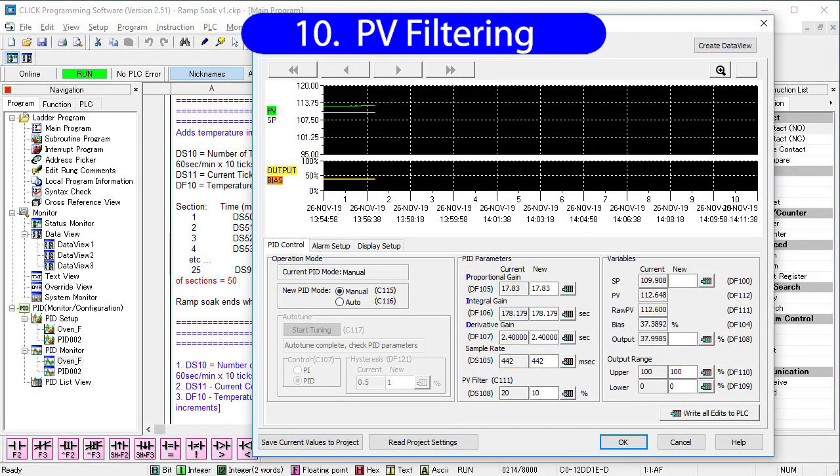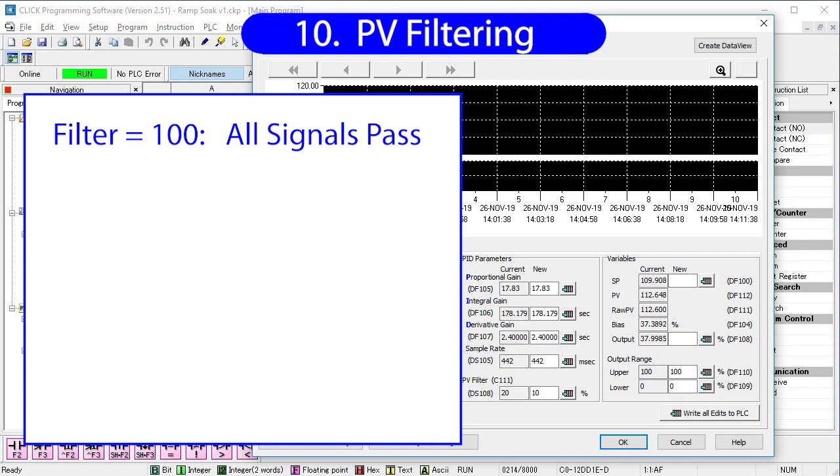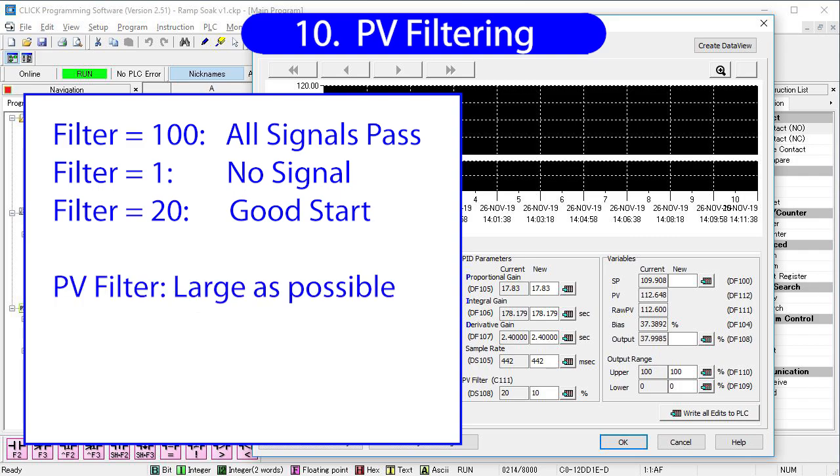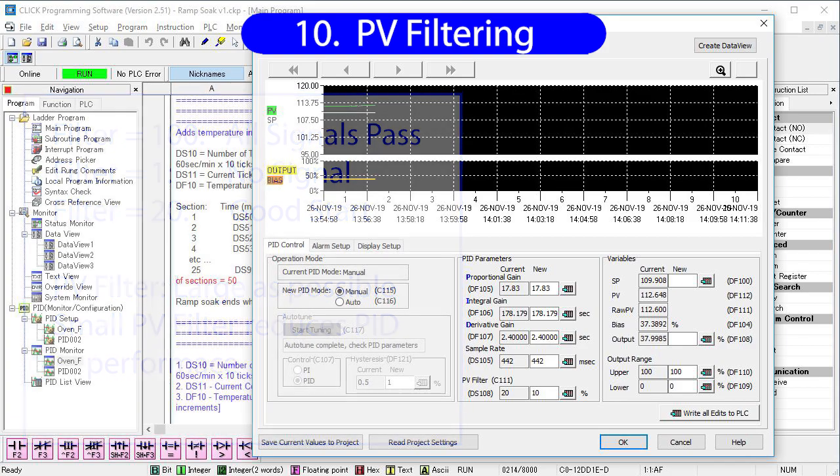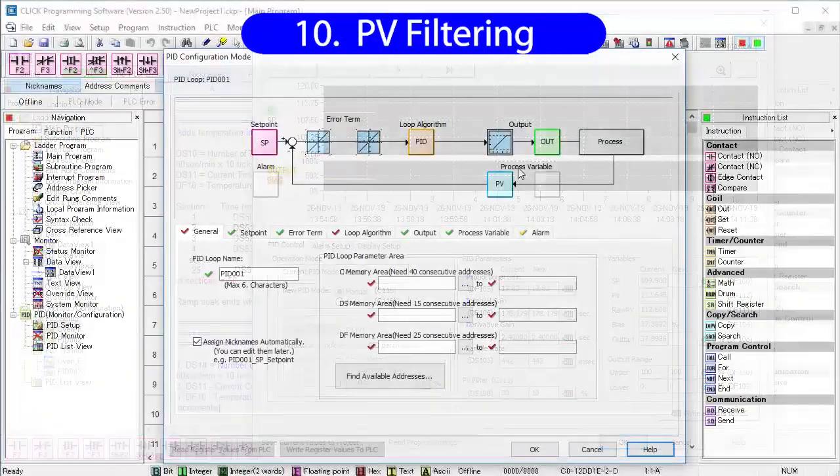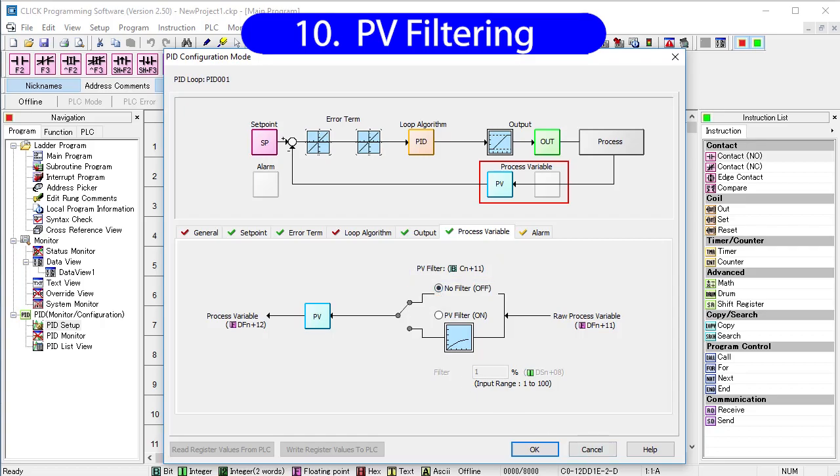Noise can really mess with AutoTune. This filter option allows you to add filtering to the process variable before it gets to the PID algorithm. Just remember that a 100 here says let 100% of the signal fidelity through. So the smaller the number, the more high frequency content will be filtered out. I typically find that a filtering number of around 20 works well for my projects, so start there and experiment. Just be sure to keep the number as large as possible. Aggressive filtering will slow down the PID response. Also, note that when you set up PID, you can leave filtering disabled. If you change your mind, simply set this bit via ladder or data view and filtering will be enabled.